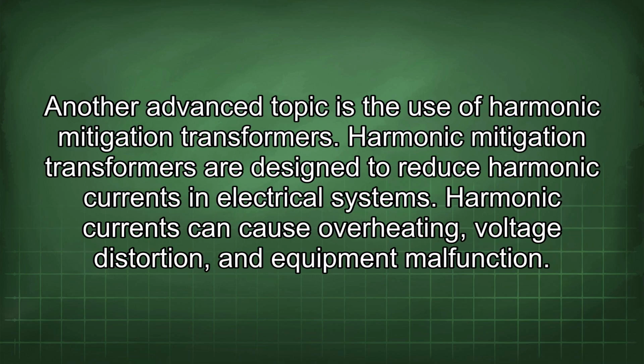Another advanced topic is the use of harmonic mitigation transformers. Harmonic mitigation transformers are designed to reduce harmonic currents in electrical systems. Harmonic currents can cause overheating, voltage distortion, and equipment malfunction.